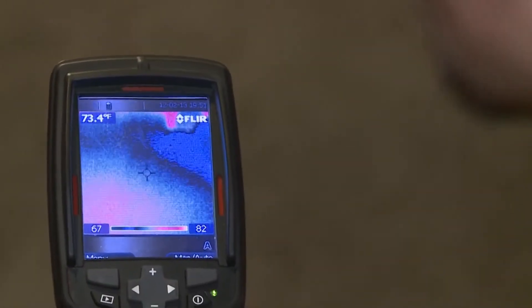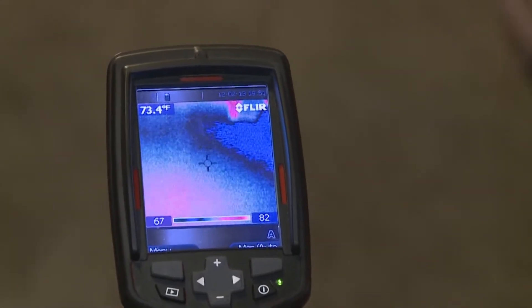When they have a sealed environment, we're eliminating a huge amount of that sucking of air in from the crawl space going up into the living space. We do temperature readings and humidity readings every time we do a maintenance on a crawl space. We're getting 68-degree lows in the coldest time of the year and 78-degree highs in the hottest. If it's 100 degrees out, as long as the door is shut, we're seeing 78 degrees.